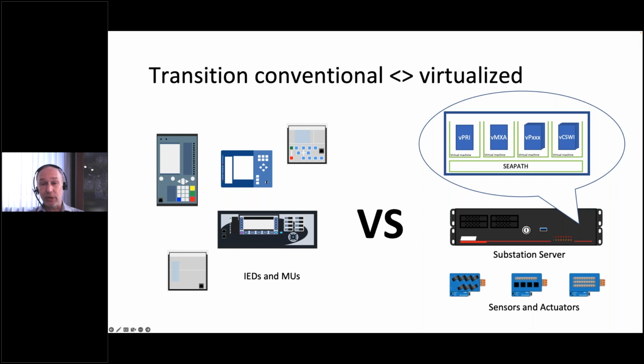61850 is designed to allocate substation functionality freely. It's no longer needed to have a TCTR, current transformer, protection functions, or control functionality in the same box. They can be physically separated in different applications and communicate over the network. This enables more flexibility in where these applications can be installed. For example, TCTR can be located in a sensor, and a PTOC protection function can be installed on a central substation computer. An application that implements a specific substation function, such as a PTOC, does exactly the same and performs just as well, or maybe even better, than its counterpart in a traditional IED. In the end, it's all software.